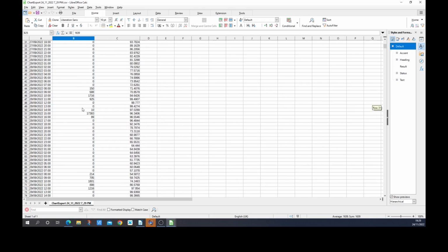But as we go down the days, you see these large numbers. I mean, you can't get 17 kilowatts in a single hour. And then you scroll down a bit more, you see 25 kilowatts, and then 40 kilowatt hours. And it occurred to me that they're actually conflating two data sets in the same data stream. You've got hourly charged energy, and then you've got total accumulated charged energy.